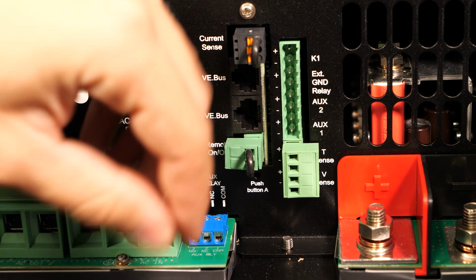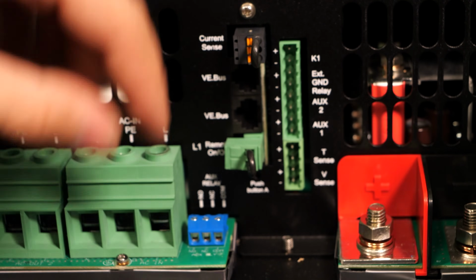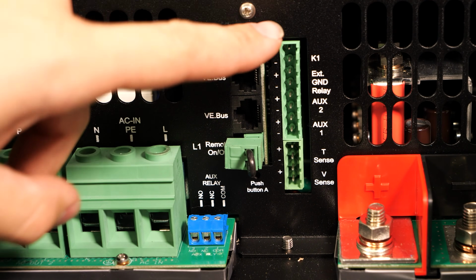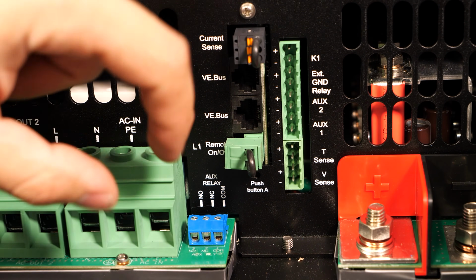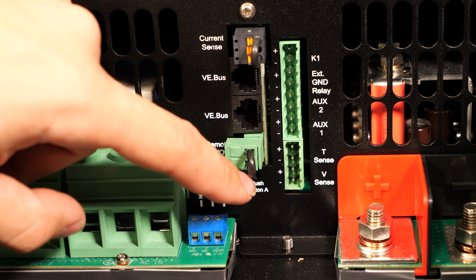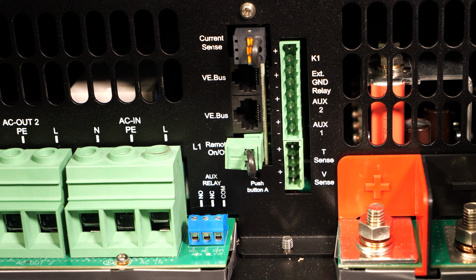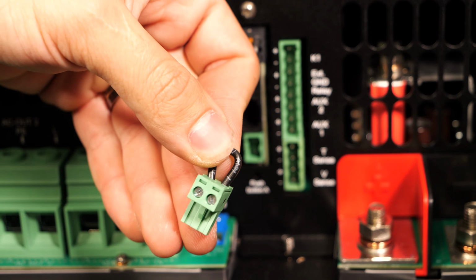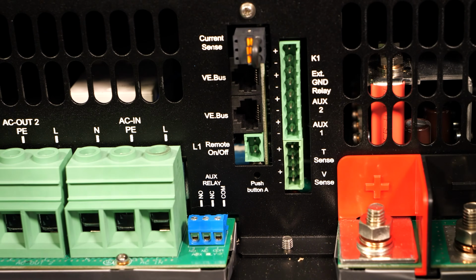In the wiring compartment, we have a few terminal bars here. If I unplug the terminal strips, you'll see the labeling. This is set up where you can use external ground relays, auxiliary relays, remote temperature and voltage sense, and this little one right here, this 2-pin plug, you can wire into a switch to make a remote power on-off.